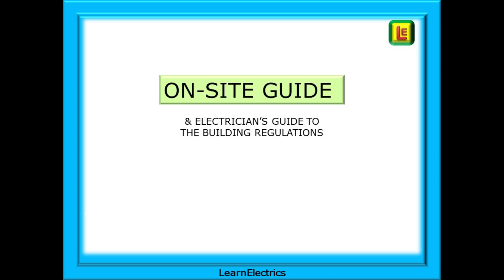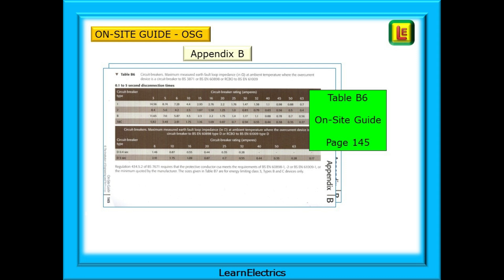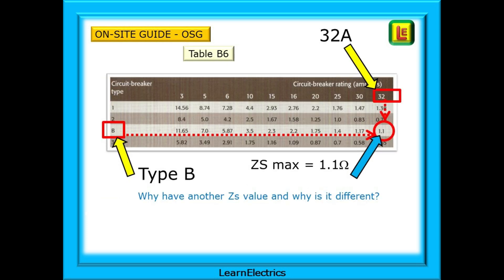Now we can look at the on-site guide and the ZS values are the same numbers as in the electrician's guide to the building regulations. Look at appendix B of the on-site guide. And on page 145 we have table B6 as shown here. We are staying with our 32 amp type B circuit breaker so find type B on the left shown in the red box and travel along the row until you come to the column ZS maximum.